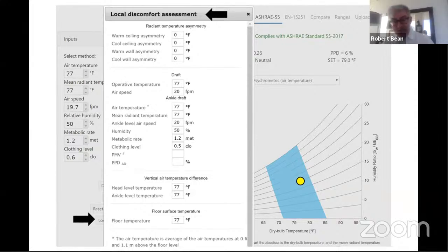And now we start looking at surface temperatures, which is the radiant asymmetry. So when someone is, say, for example, at a desk, seated, exposed to shortwave radiation from the sun, the front of their body will experience solar loading, and they might be in a space that's air conditioned. So the back of them might be cool. So whenever you have somebody that has a high surface temperature in front of them and a cool surface temperature behind them, they experience what's called radiant asymmetry. That is the radiant temperature difference between them. And when it gets too extreme, they will complain. Same thing with the floors to walls, or sorry, floor to ceilings.